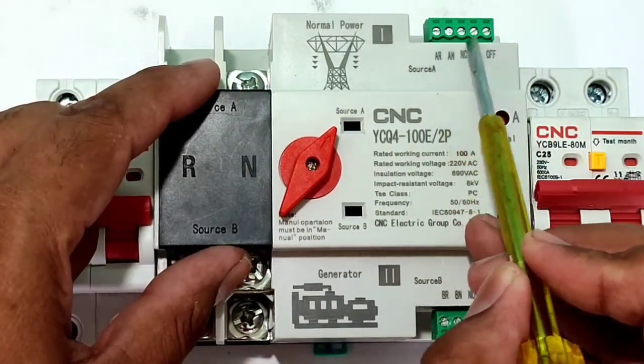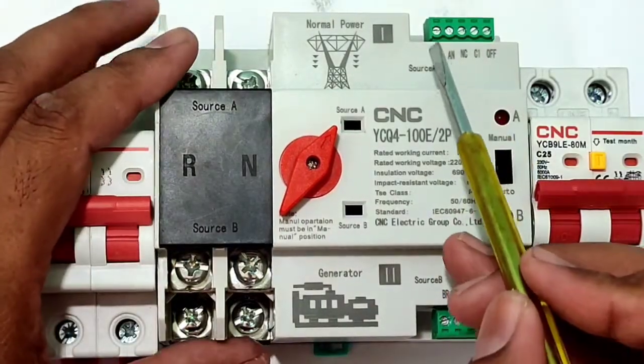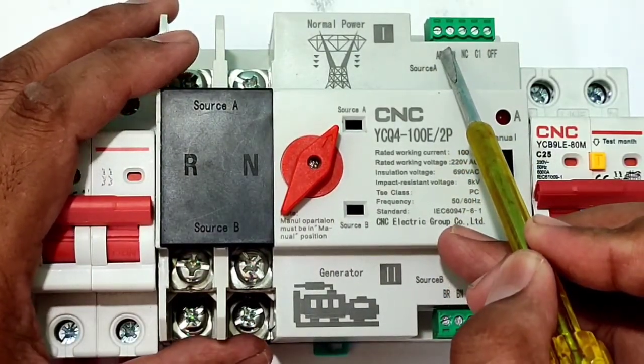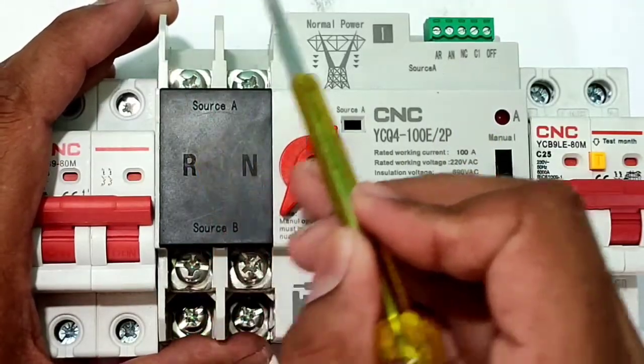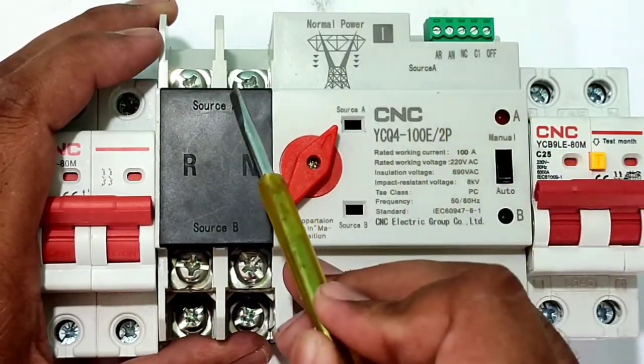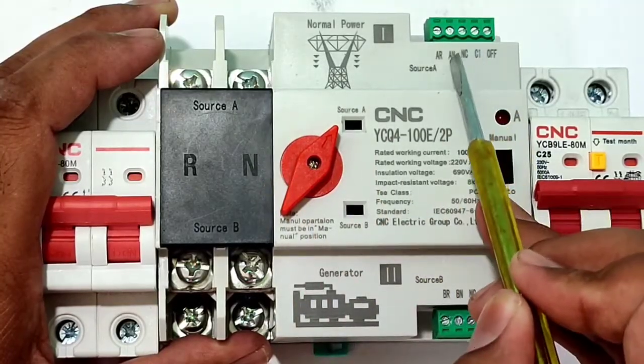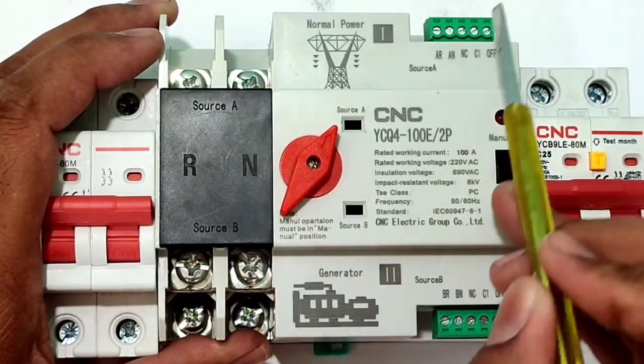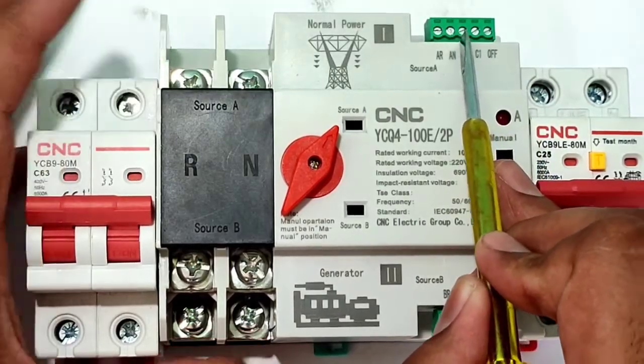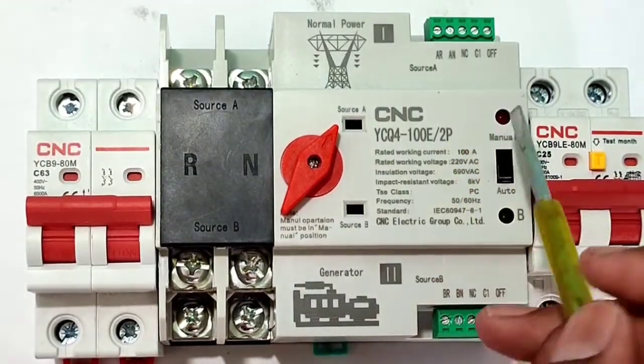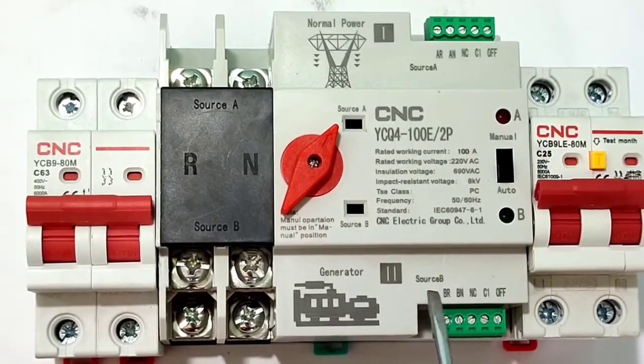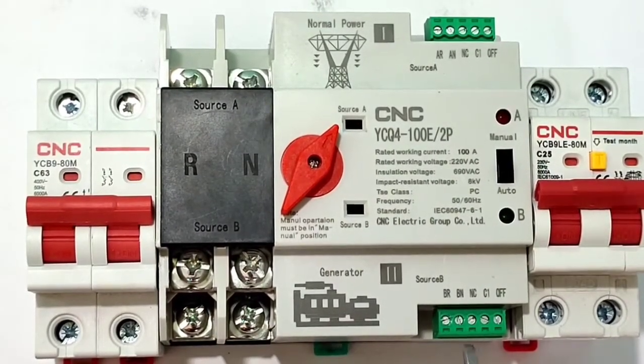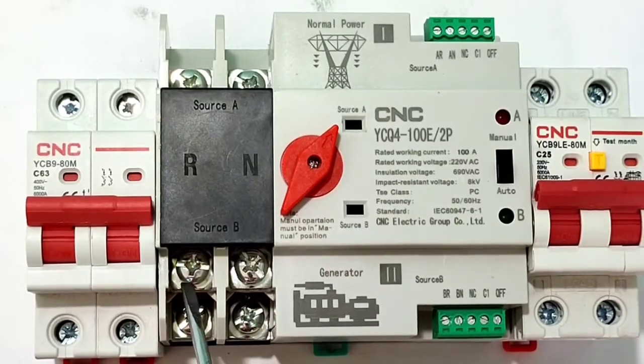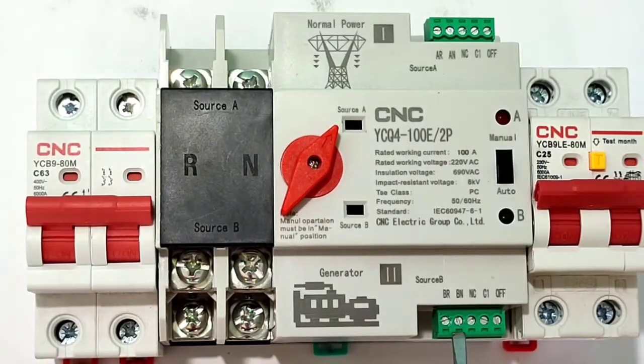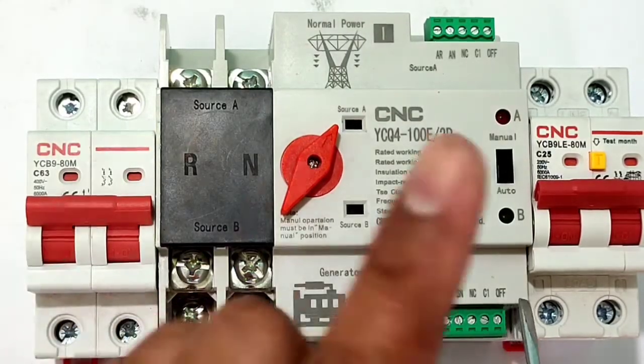Now see the control wiring. You can see here AR and AN. Connect one connector from the AR terminal to the source AR terminal. Now for neutral, we connect the N terminal here to this AN terminal. N is the neutral and R is the phase wire. So connect one connector from AR to R and AN to N. Now the same connection for source B: we connect BR to one connector here, and BN to a neutral connector here. We connect BN to the neutral connector.